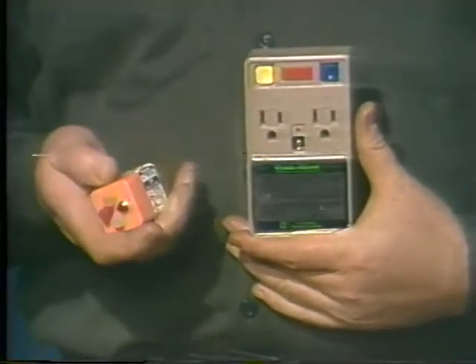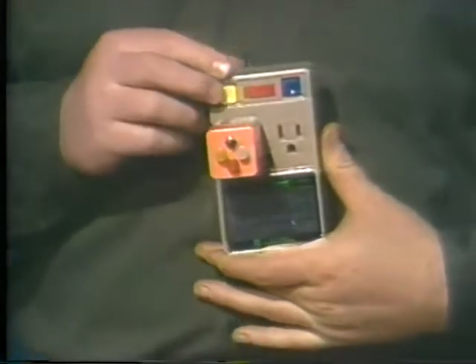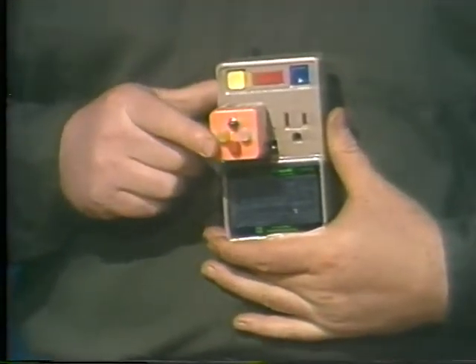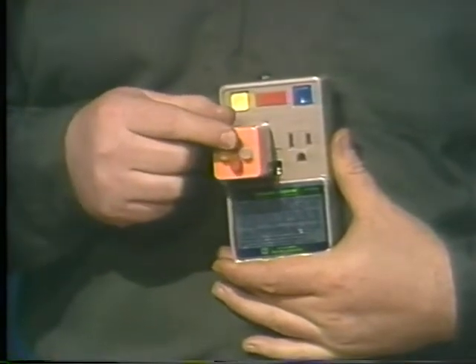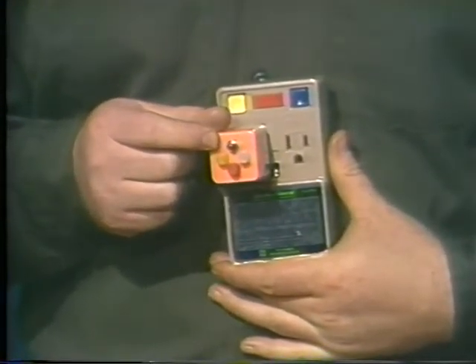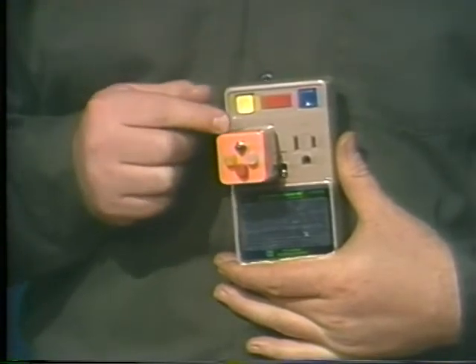Portable ground fault interrupters are getting to be fairly common. They're about the best thing we've got for preventing shocks due to ground faults in electrical tools. But they're not foolproof. If a receptacle's not wired or grounded correctly, a GFI can't work the way it's supposed to. And that's where this comes in. Just by sticking it in the socket, like so, you can check the polarity and ground. And with this button, you can test a portable GFI, or even test a GFI that's permanently wired into the electrical system.